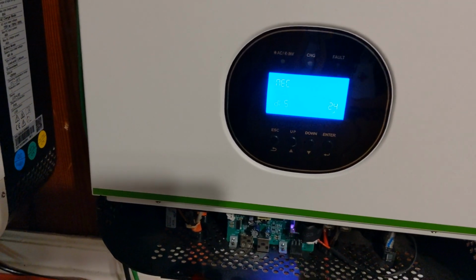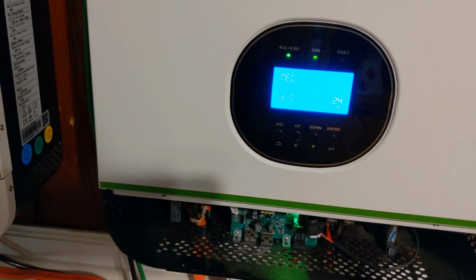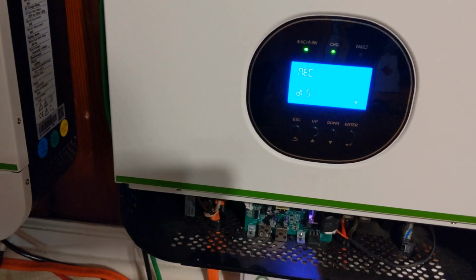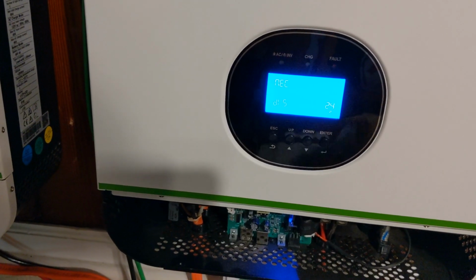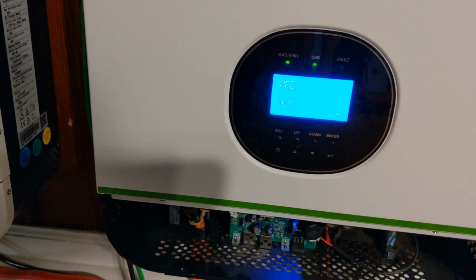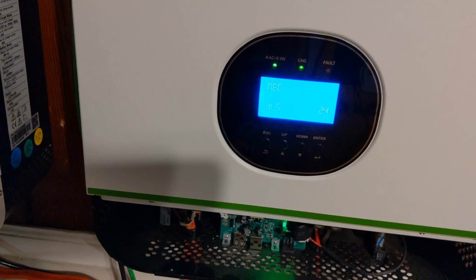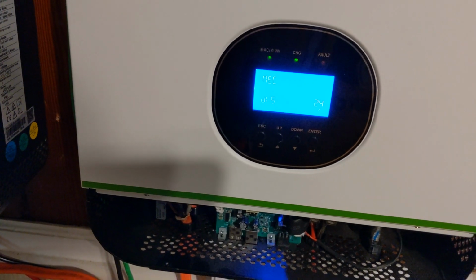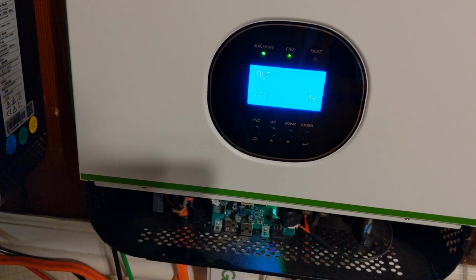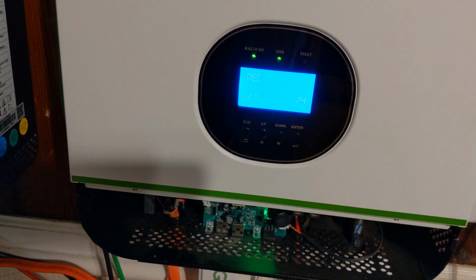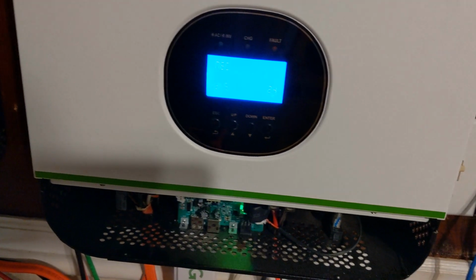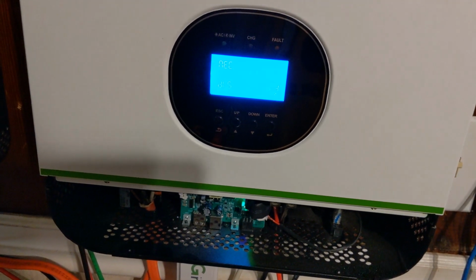And I highly, highly, highly recommend that after you set those settings, you have all of your loads that may be connected to this thing shut off. So in the case of this, the output goes to my little sub panel. Everything in that sub panel will be shut off before you do any settings. So you shut everything off, set your settings, turn the inverter on, go to that panel, and make sure that you have proper split phase power coming in before you turn anything back on. That way you don't run the risk of damaging anything or anything of that sort.